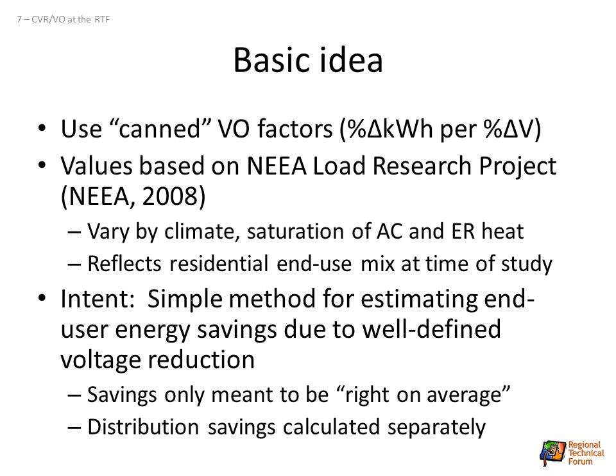So we know some things that come along with that simplification. One, these savings are only meant to be right on average. You can't expect the VO factor from a table, as the SMUD study shows, to necessarily apply to every one of your feeders. So that 'right on average' standard is something the RTF finds acceptable for savings claims within the regulatory process, but whether or not that's an acceptable standard for, say, a capital improvement case on a grid improvement project, the RTF doesn't have any comment on that.